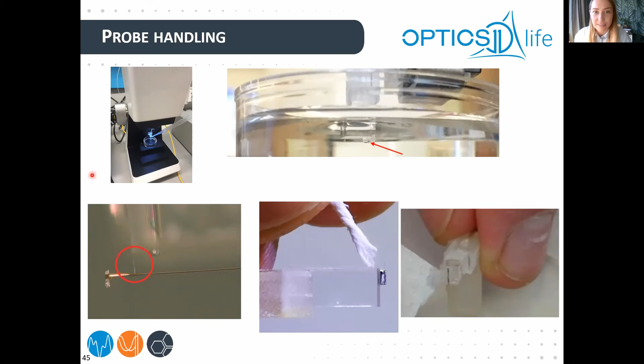Now, any of these things can happen, but luckily you do have an interferometer, which is basically your eyes. If the cantilever is stuck, you won't have a signal when you do the wavelength scan, or you lose the signal during the measurements because that happened. If you have a bubble, you will have a very noisy signal. So the interferometer just helps you to see what happens. And the best practice is always to run a lot of liquid over the probe so that it detaches and is in a good position.